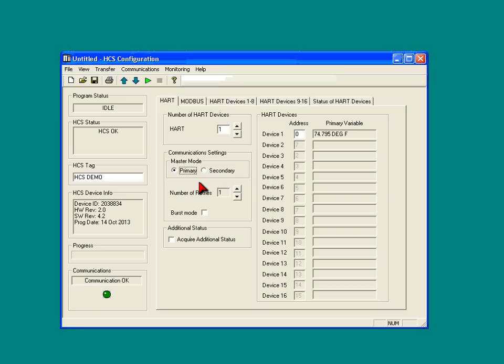Be aware that if a technician then walks up to the network and connects a HART handheld device to it, the HART handheld device is also a HART master, and you're going to have a problem immediately. And you won't know where it's coming from. It's because he connected, he's a master, something's got to go. One of the masters has to get off the network.